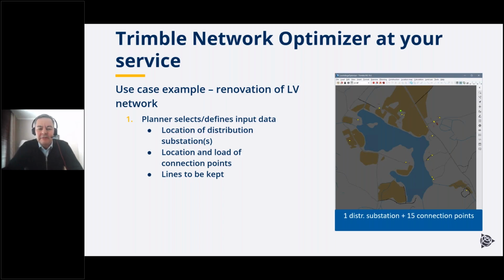In this low voltage case, the planner should select or add the location of the distribution substation or substations, then the low voltage connection points, their location plus consumption or production information if there are distributed energy resources installed. In case of renovation, they should also define what existing lines should be kept in the future.